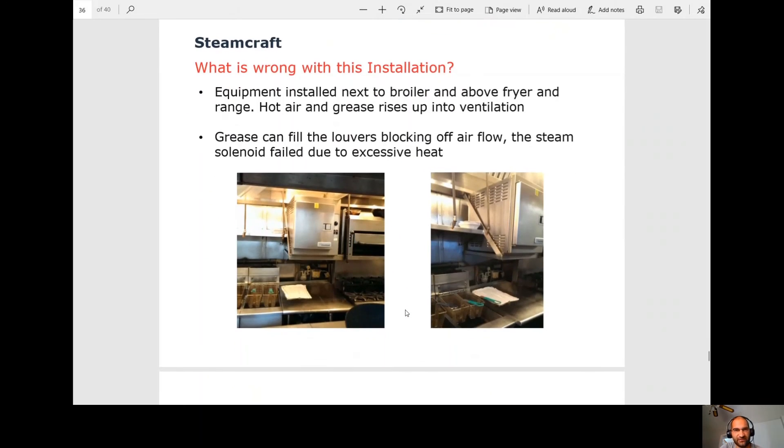So now let's go into some bad installations. So this one is right next to a fryer and a salamander, and then also the grill on the bottom. So what happens is grease can fill the louvers, blocking airflow. As we know, airflow is very important for electrical components. In this case, the steam solenoid failed because of too much heat in here. So this would be an incorrect installation. There are clearances that we need to follow.